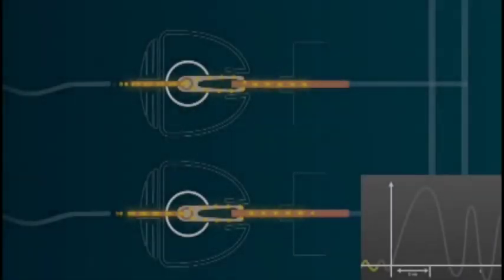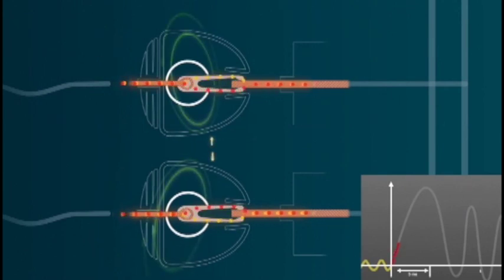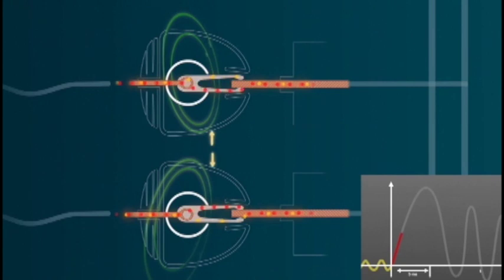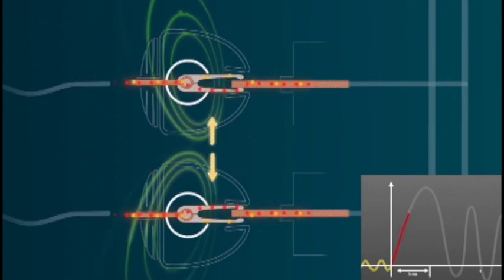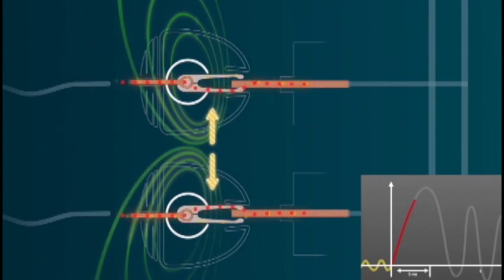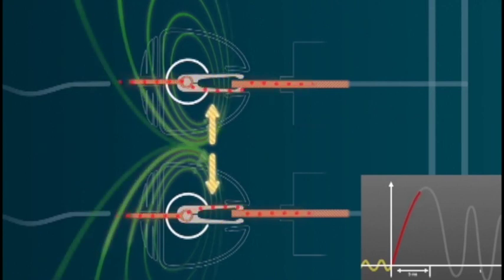The magnetic force between power plugs is another interfering effect that may cause a failure of the finger contacts. The impact of this magnetic field can be even more critical because, in most cases, the plug systems are simply supported to compensate mechanical tolerances only.